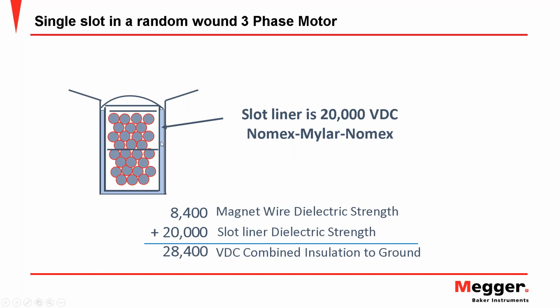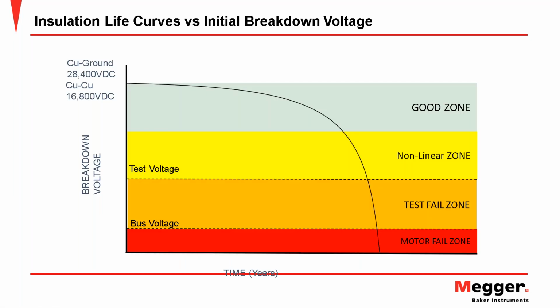And now I wouldn't suggest we ever test a 460 volt motor to that, and we couldn't, because what would end up happening is we'd ionize the air around the outside of the coils, and we'd get partial discharge from that external ionization to ground, and that would cause our current to trip, but it wouldn't be breaking through any insulation barriers. It'd be externally to the portions of the coils that are outside of the slot where a lot of that discharge would occur. And again, it's not super valuable. We're not stressing that level, so there's no need to test to that high voltage level routinely. But what we want to do is test to the operational stress. Okay.